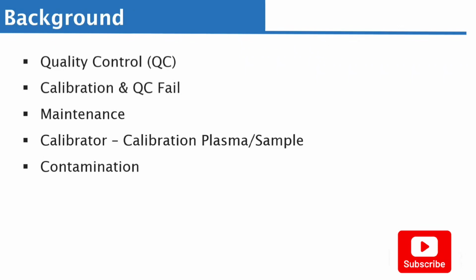But there are also other situations whereby you want to do quality control. The same way you analyze the patient sample is the same way you should be able to analyze the control sample. And the same way you do that is also how you are going to do your calibration, because your calibration is going to use a calibration sample, like maybe calibration plasma or calibration serum or calibration blood, as the case may be. The only difference is this: when it comes to the analyzer, you've got to tell the analyzer what you are doing. So if it is control you are doing, you have to go to the control sign or icon and identify that for the analyzer to know this is what I'm doing right now. If it is calibration, you also need to let the analyzer know that you are doing calibration.